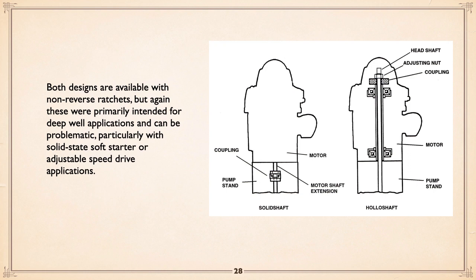Now here's what they actually look like. You can get ratchets that prevent the motor from spinning other than in the direction that pumps typically go. But basically, these motors are intended for deep well applications, and upthrust can be problematic, particularly with solid state starters or adjustable speed drive applications. That's the one problem with the ratchets. The ratchets are noisy as they come off speed, and it's not doing them any good. So if you've got a soft start, you're going to hear it, particularly when you shut the motor down. You will hear that thing rattling away. Similarly with an adjustable speed drive, as the motor slows, you get noise.